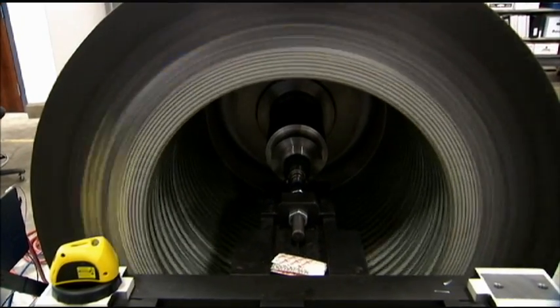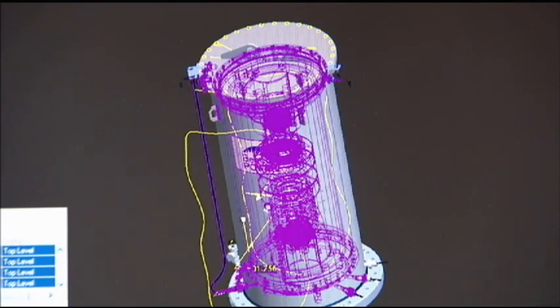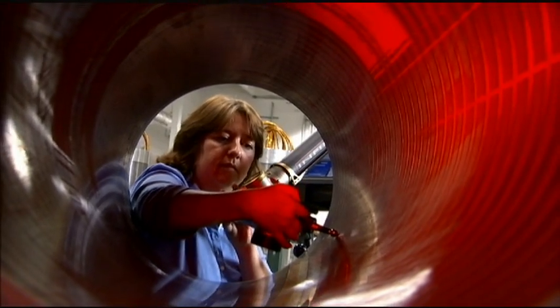The flywheel itself runs at very high speeds. It ranges in the Gen 4 flywheel between 8,000 and 16,000 RPM. At 16,000 RPM, the surface speed is like Mach 2, so there's no air in there, which makes that less relevant. Nonetheless, it's operating at very, very high speed. We also have a vacuum system and many other systems that maintain its safety and ability to operate successfully over 20 years.